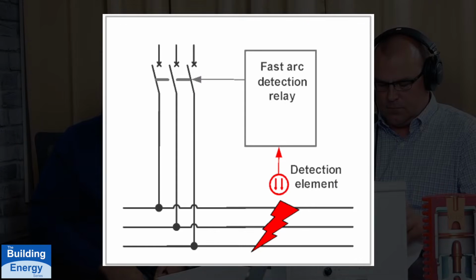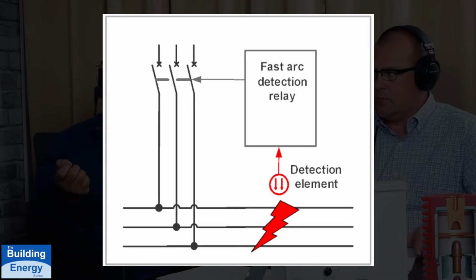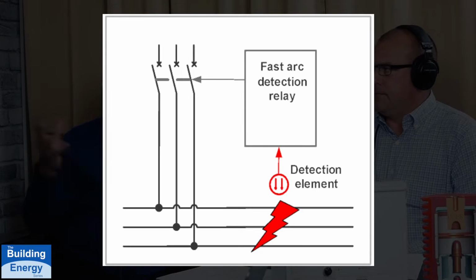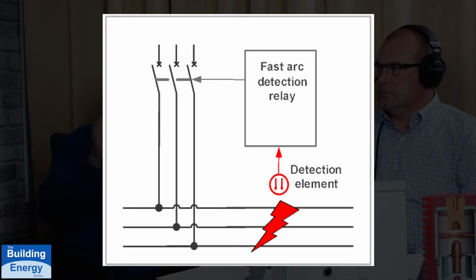So when it comes to active arc flash mitigation, there are a number of different techniques that folks in this industry are employing. First could be arc flash protection relays, which are designed to take an optical input and a current signal input. Anytime you have an arc flash, a huge amount of energy is released, and a lot of light. Up to 10 million lux can be released in an arc flash, which could be very damaging to the eyes. The relays incorporate lens sensors or fiber optic sensors, depending on the technology, that pick up the light signal.